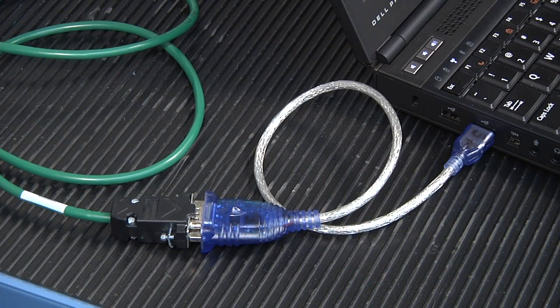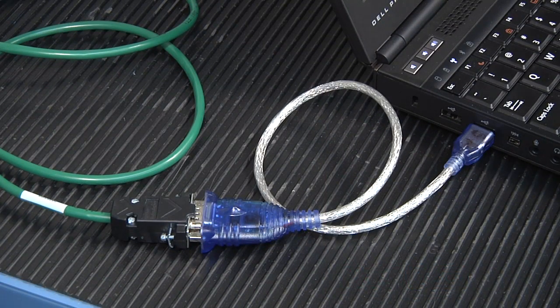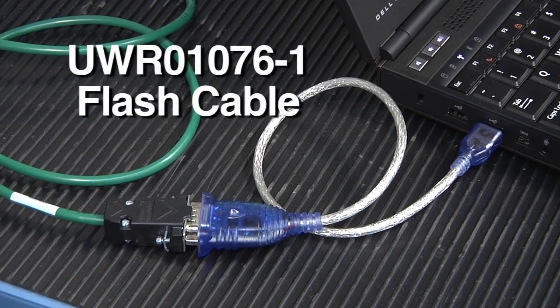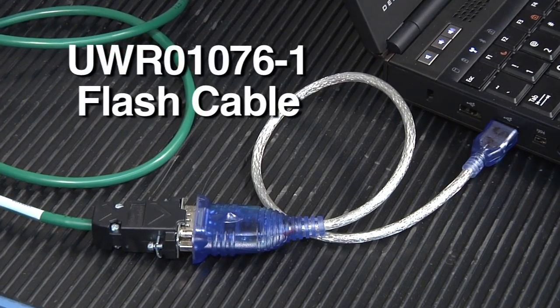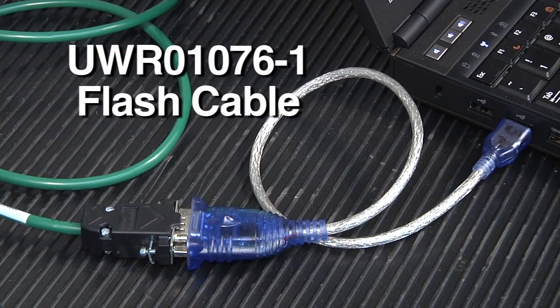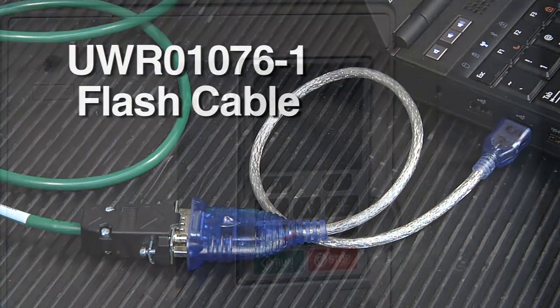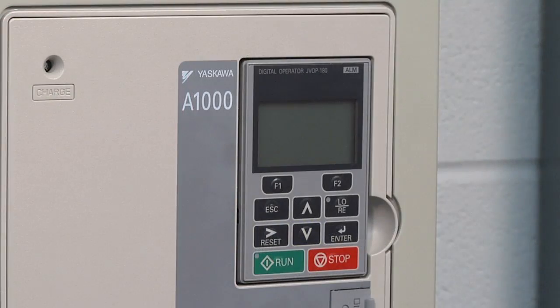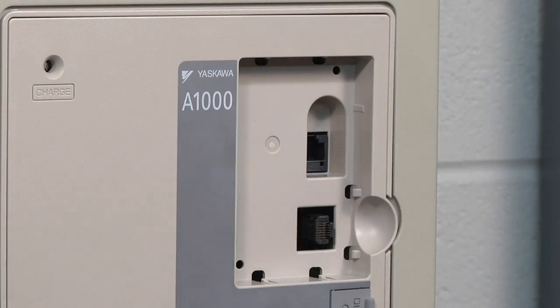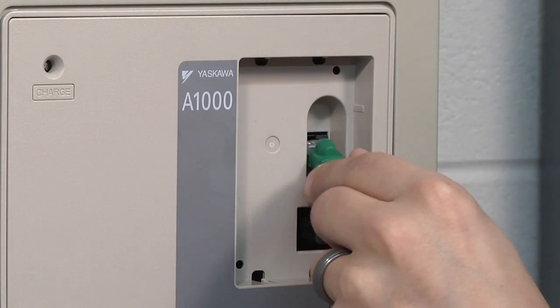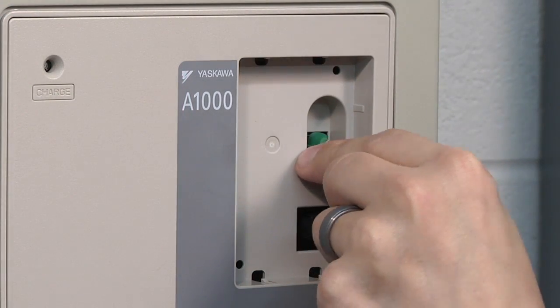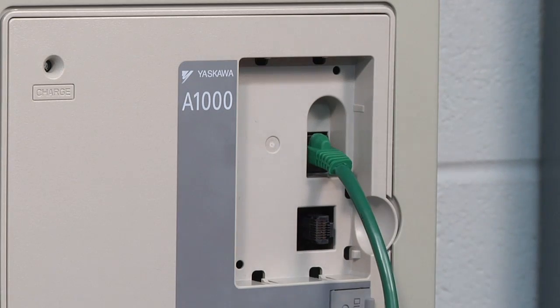Connect the Flash Cable to the computer. Yaskawa recommends using a UWR-01076-1 Flash Cable. Remove the digital operator, then connect the boot flash cable to the drive in the same port where the digital operator was connected.